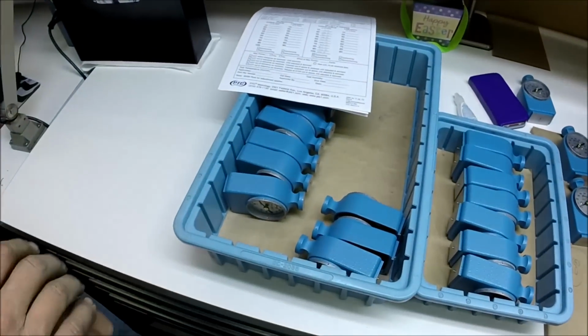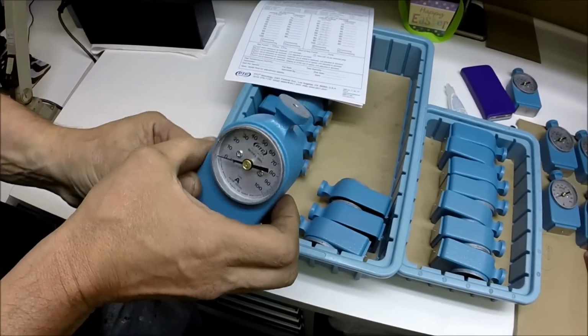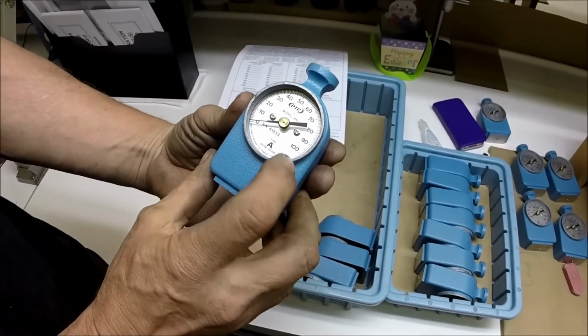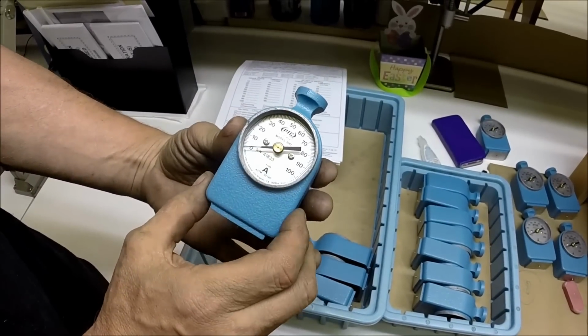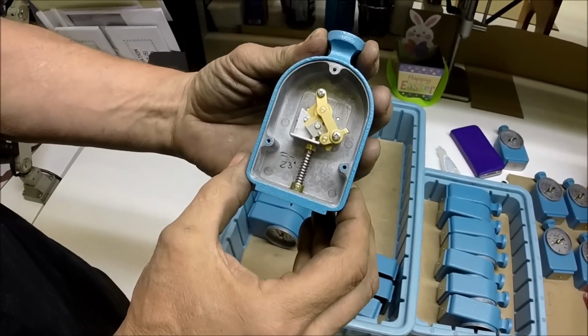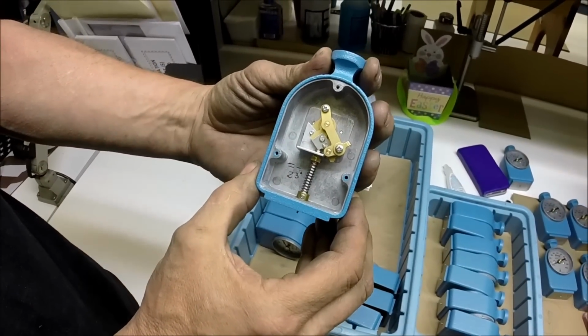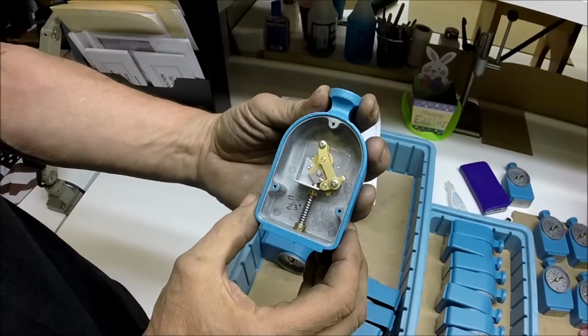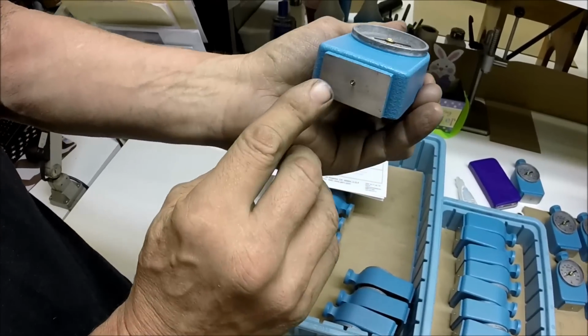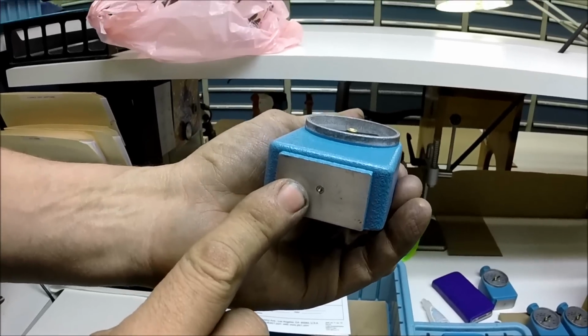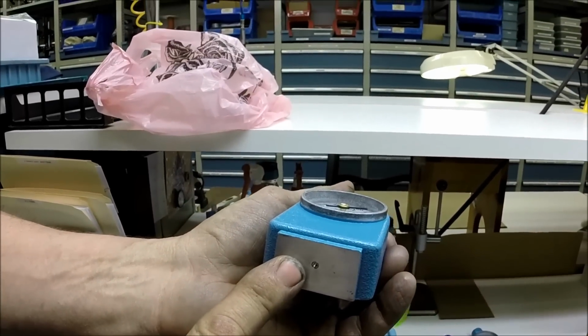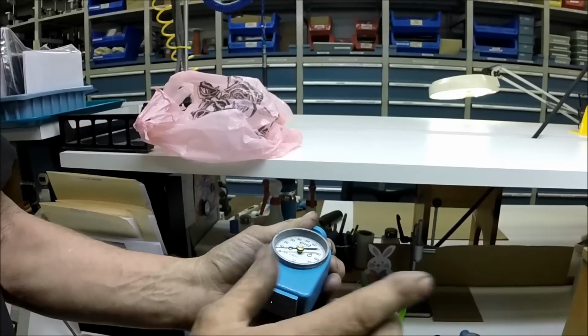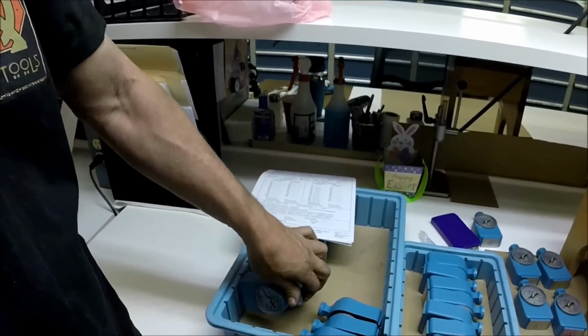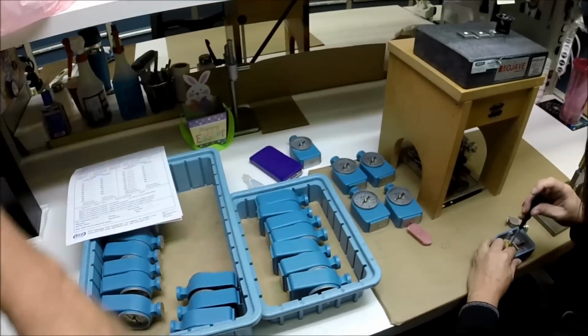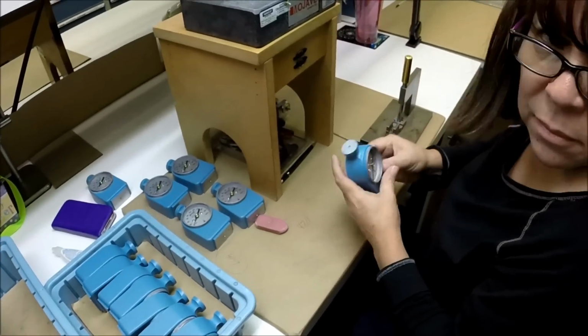Where are you in the calibration? Yes. So these durometers are pretty much fully assembled. You have the faceplate, the pointer, the interior mechanism, the precision spring and dial indicator movement. It has a geometry on the indenter that's specified by an ASTM specification. And from this stage, Isabel is checking them and checking the extension on a surface plate with precision gauge blocks.